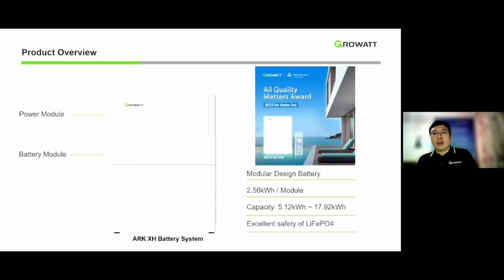Now the batteries we use for this TL-XH inverter, called ARK-XH, are approved and fully qualified to be installed in Australia. We've listed these batteries in the South Australia Home Battery Scheme and also the Victoria Battery Rebate. It's a modularized design—each module is 2.56 kilowatt hours. The minimum you put is 2, and the maximum is 7, giving you up to 18 kilowatt hours of battery capacity.